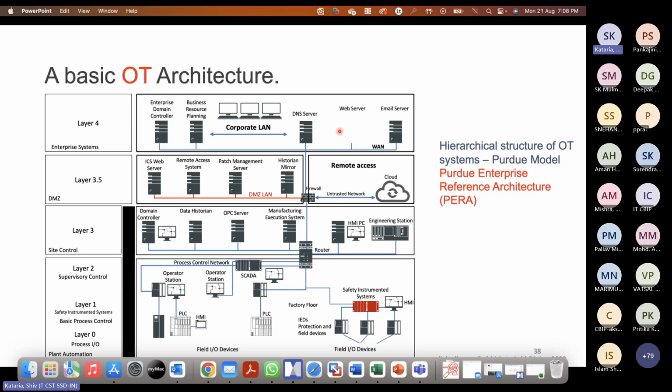it depends on the kind of system. In the new substation systems that we typically configure, we put both. We put McAfee's host-based intrusion detection system as well, and on the network side also we put it. But on the legacy systems, since we have resource constraints and the IDS will be reading into your system continuously, it will require some resources. So there, we typically don't put the host-based; we put the network-based IDS through passive network monitoring. Does that answer your question?